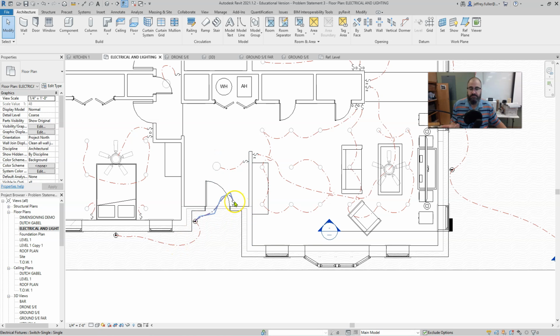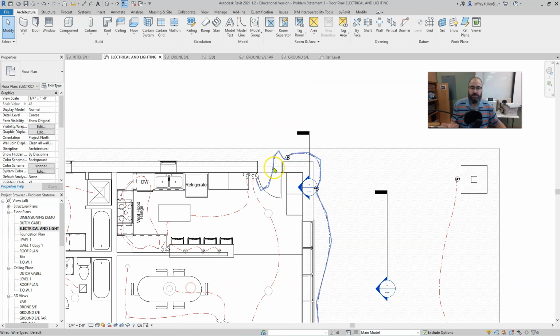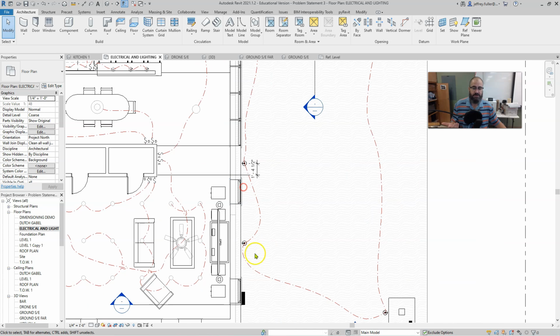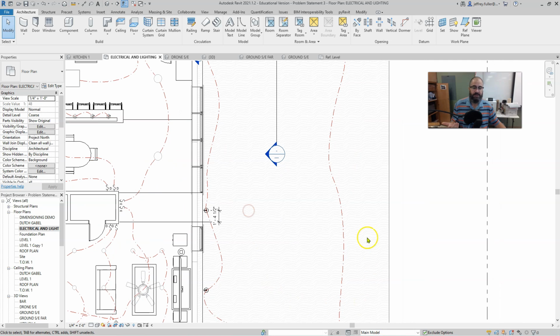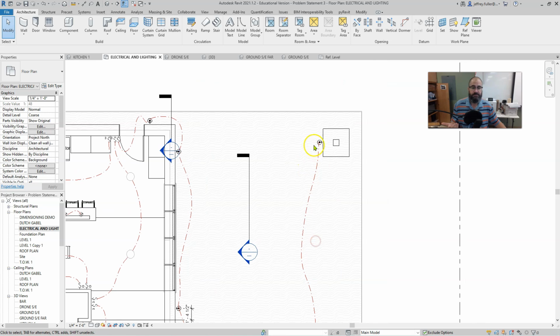These are exterior lights, switch right here by the door, going through the door opening to each light fixture. And then over here also on the back door, I have a light fixture right outside the back door that's controlled by this switch. And of course, it also controls all the light fixtures on the carport. Okay, so I have a whole loop of wire that goes all the way around to the very last fixture, which is right here, and that's where the wire stops.